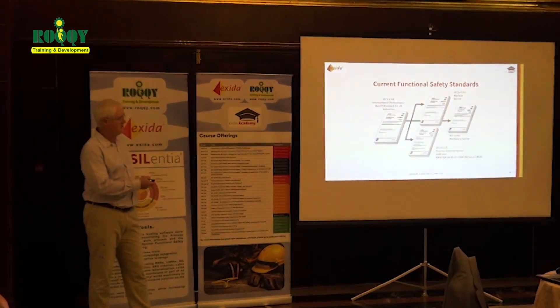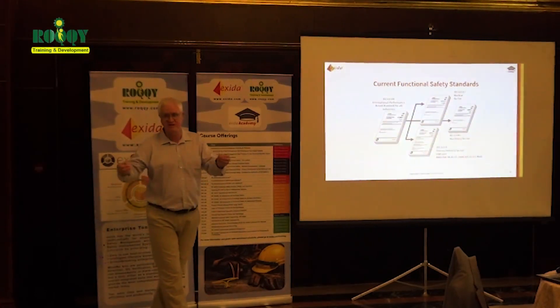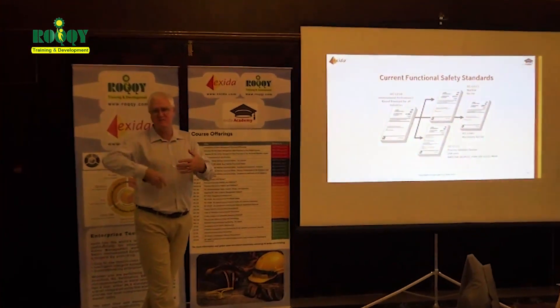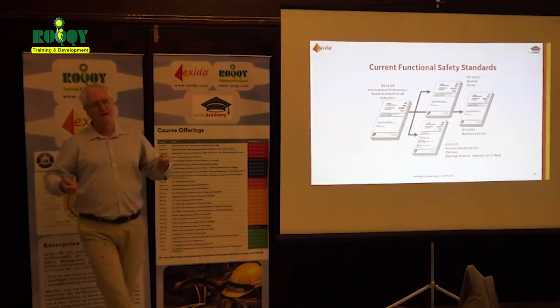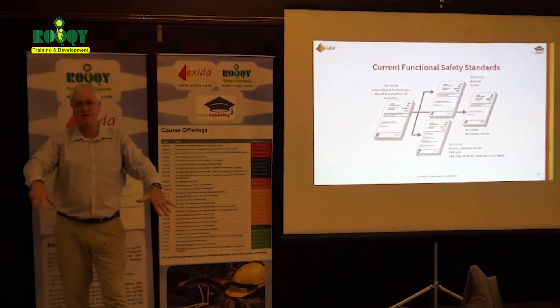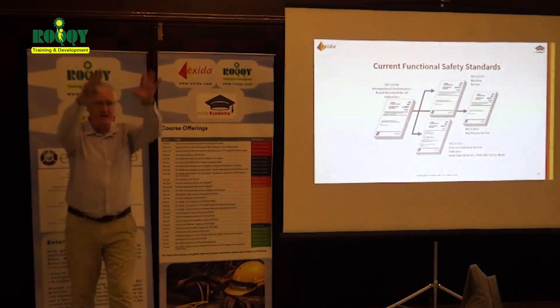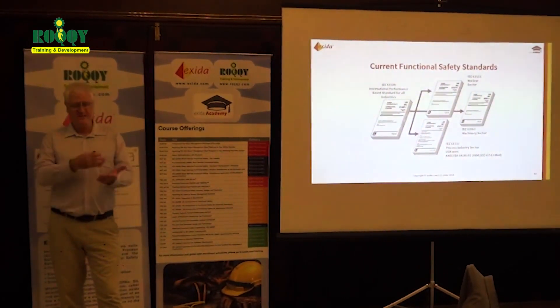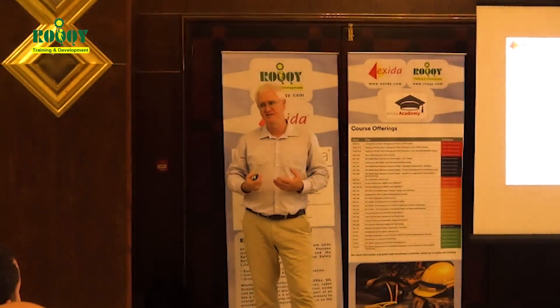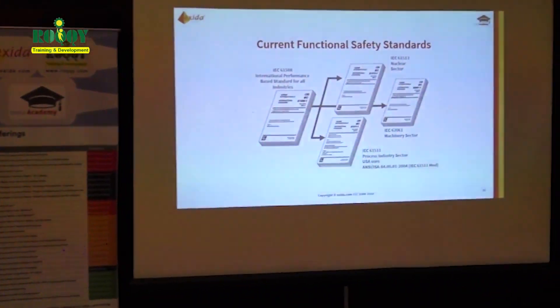The difference between IEC 62061 and IEC 61511 is that machinery safety deals with situations where people are always near the hazard — presses, lathes, cutting equipment. For example, when stamping a car bonnet, operators are always in close proximity and risk crushing or pinching injuries. The process industry, covered by IEC 61511, deals with the big events: explosions and toxic releases on refineries and large chemical plants.